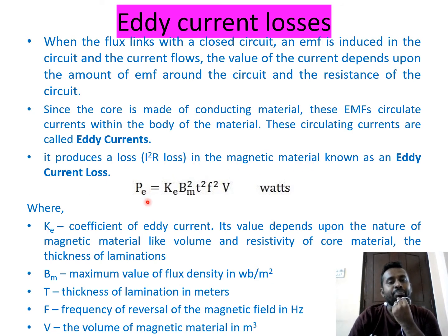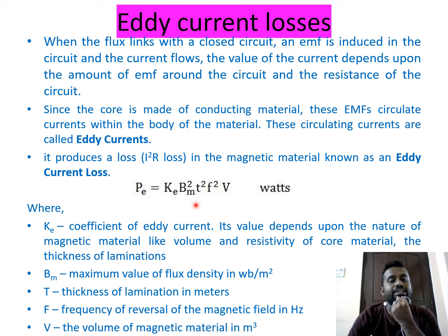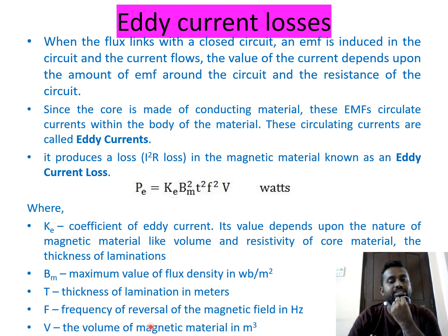Eddy currents produce an I²R loss in the magnetic material known as eddy current loss, given by: Pe = Ke × Bmax² × t² × f² × V, where Ke is the coefficient of eddy current depending on the nature and resistivity of the magnetic material, Bmax is the maximum flux density (in Wb/m² or Tesla), t is the thickness of laminations, f is the frequency, and V is the volume.